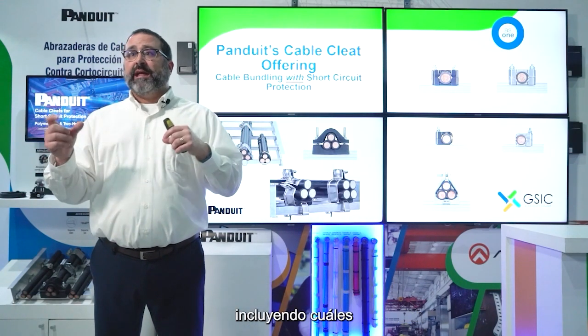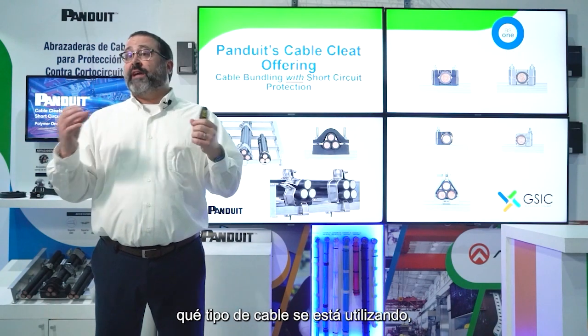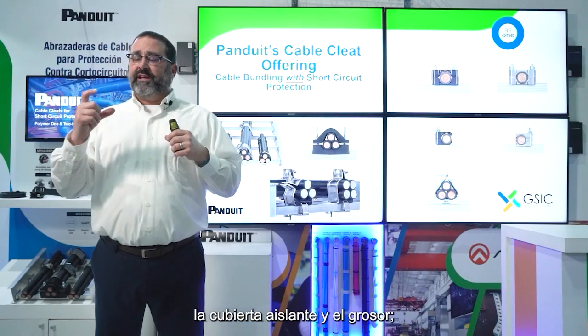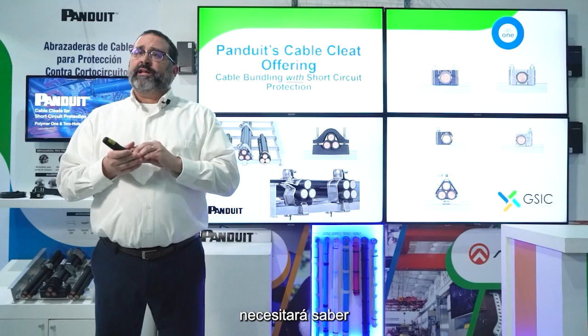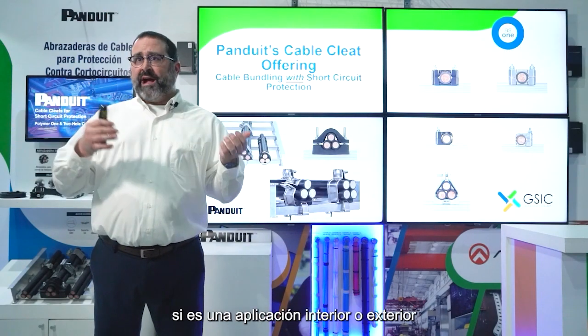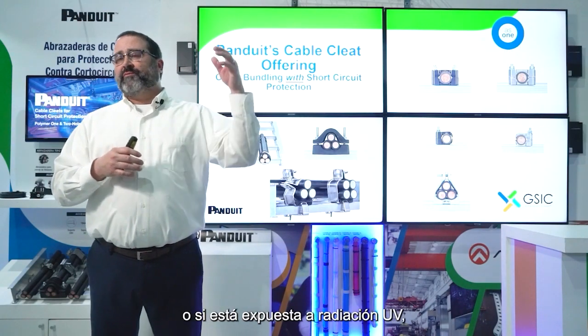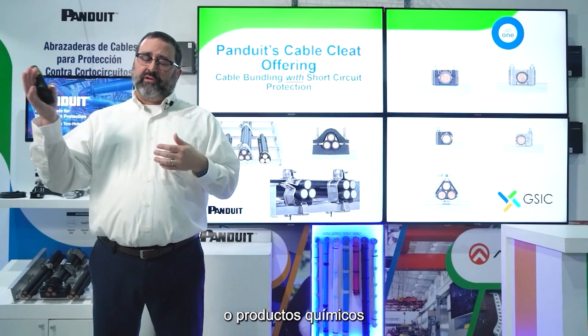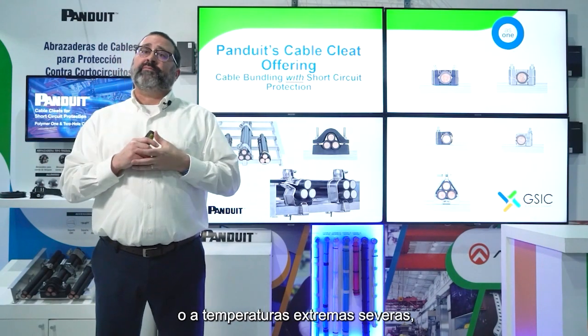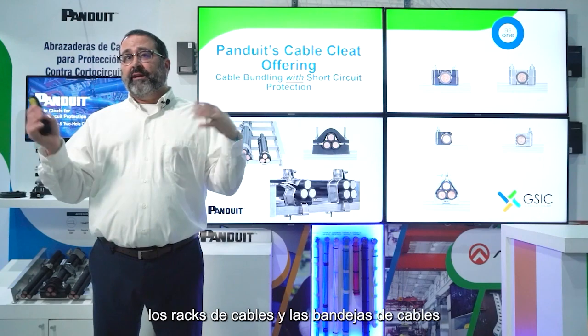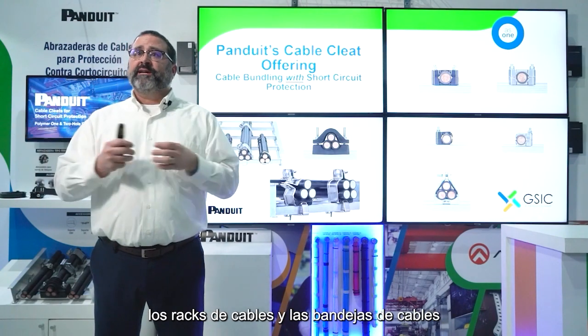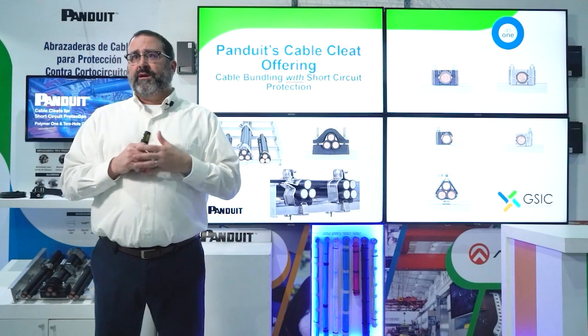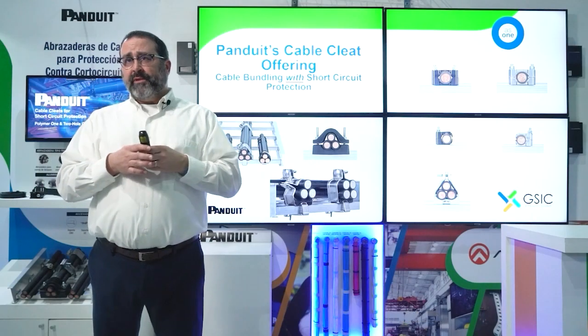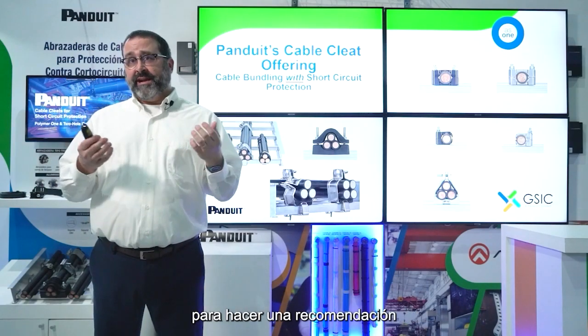It includes what the cable diameters are, what type of cable is being used, the insulation jacket and thickness. You're going to need to know whether it's an indoor or outdoor application, whether it's exposed to UV or chemicals or harsh temperature extremes. And then you're going to need to know the cable rack and cable tray the product's being installed in. All of those inputs are needed in order to make a recommendation.